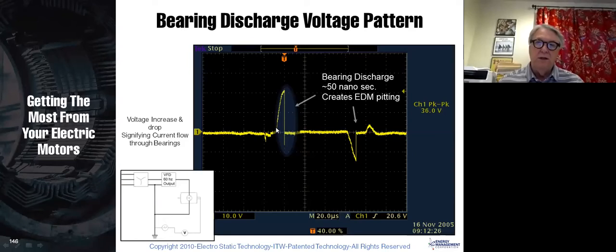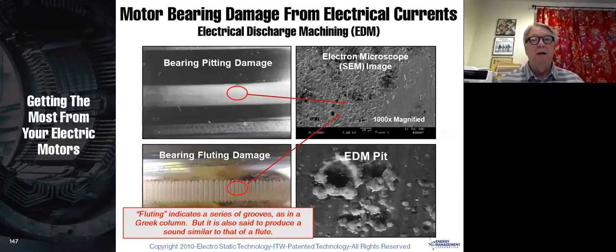You can see that the voltage increases, and all of a sudden, right here, it arcs across, and so you can see the voltage drop suddenly because it has discharged through the bearing. This is bearing pitting damage. So if you look at it under an electron microscope, then you will see this pitting occurring in the lower right. Obviously, we don't want to see that in our bearings.